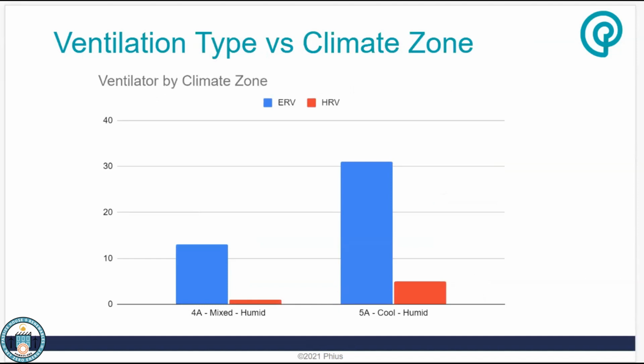So energy recovery ventilators versus heat recovery ventilators. So for people who aren't familiar, energy recovery ventilators not only recover heat from the ventilation air, they also recover moisture or humidity. So if you're in a very cold climate, like I'm in Chicago, you guys are in Massachusetts, if it's really cold and dry in the winter, you want to try and retain that indoor humidity in the cold season. So an energy recovery ventilator will do a little bit of that and try and keep some of that humidity inside of the home and help try and reduce the really dry air that we get in cold climates like that. So you can see, basically most of our projects are using energy recovery ventilators, whether it's climate zone 4A or 5A, the vast majority are ERVs.